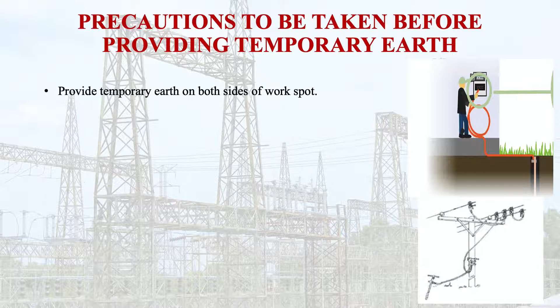While disconnecting earth, first disconnect the earth rod from the line or equipment. Ensure that the person providing the temporary earth wears rubber gloves. It is also to be ensured that the person providing the earthing is at a lower level than the line or equipment being earthed, and other persons are 6 meters away while earthing.